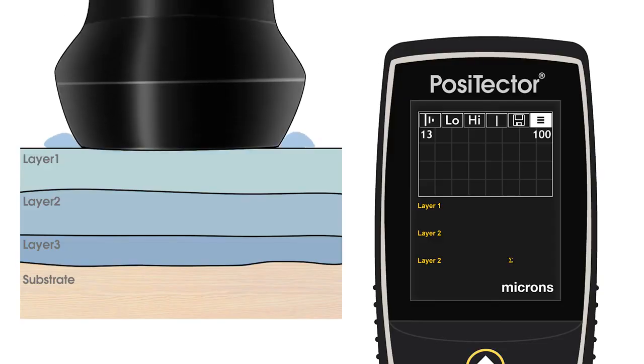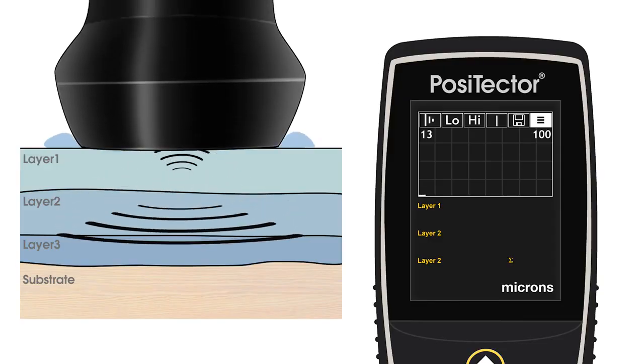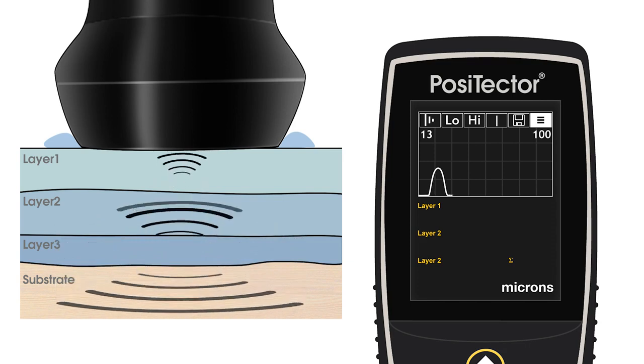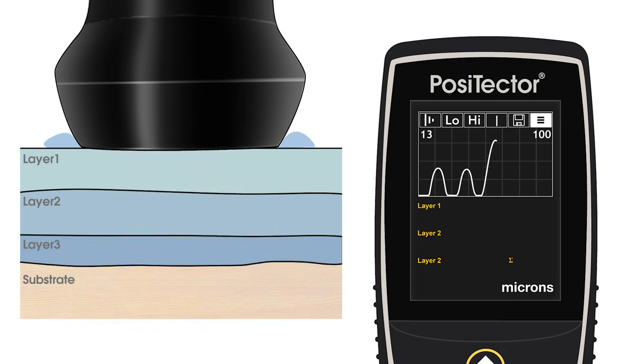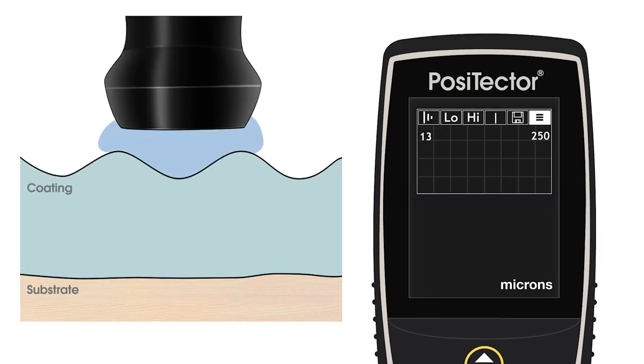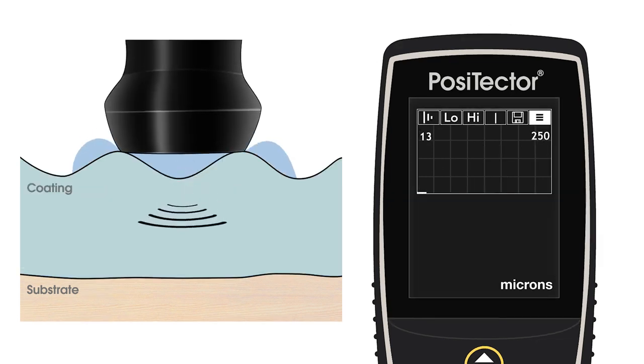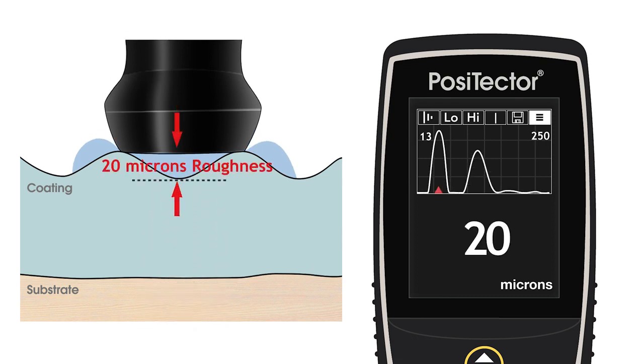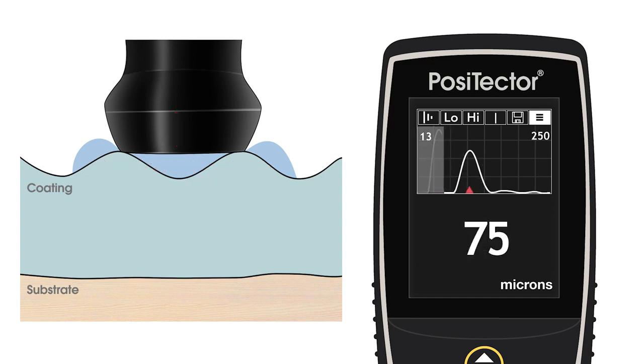The Positector 200 searches for the loudest ultrasonic echo within its measurement range and reports it as the coating thickness. In multi-layer mode, the thicknesses associated with the loudest echoes, depending on the number of layers selected, are reported as individual layer thicknesses. Applications with surface roughness can generate loud, unwanted reflections near the surface, causing the instrument to report the distance between the probe and the valleys of the surface profile, instead of the coating thickness.